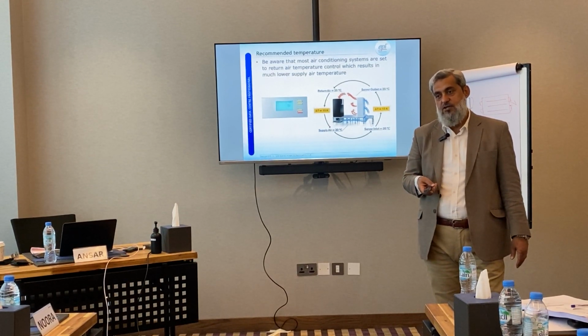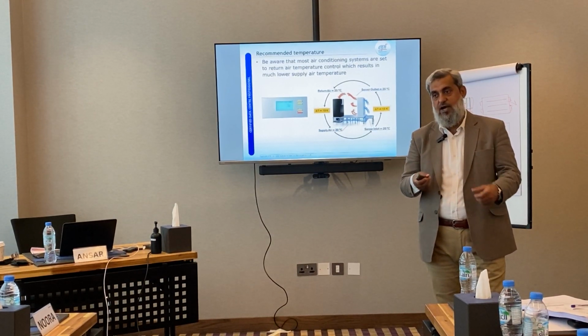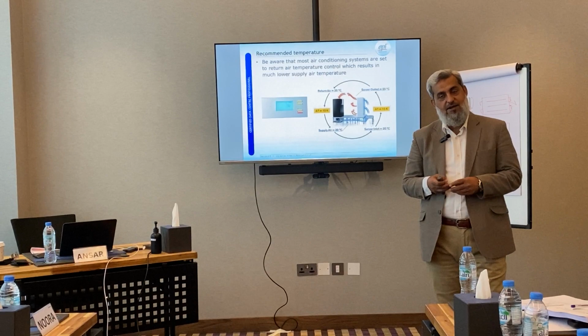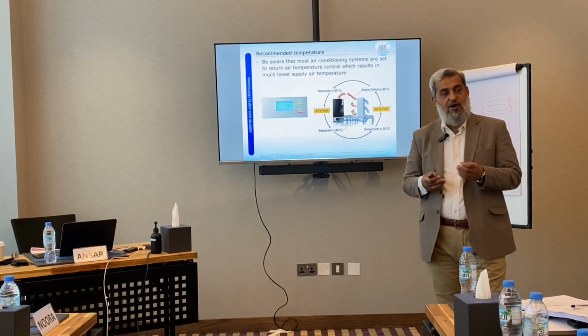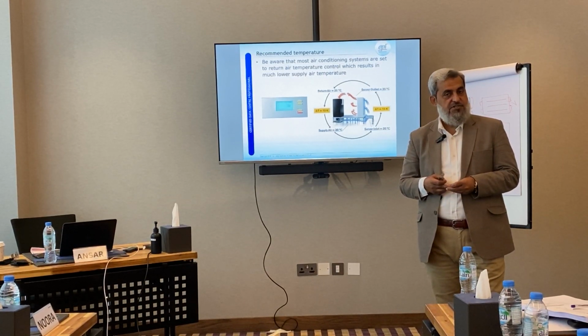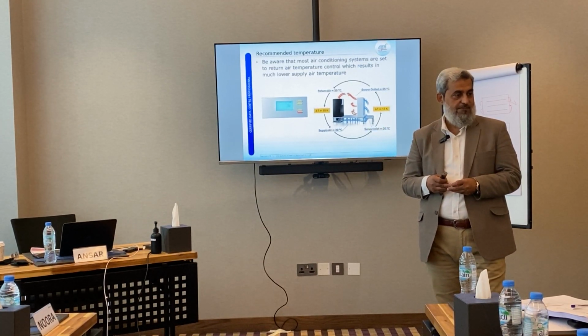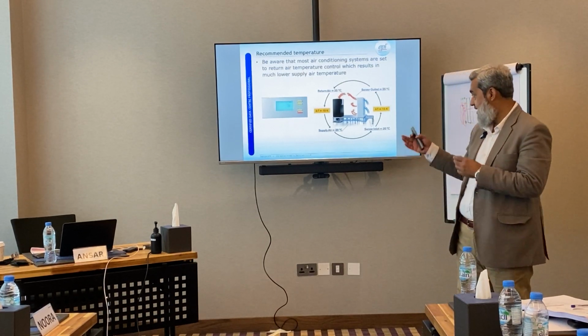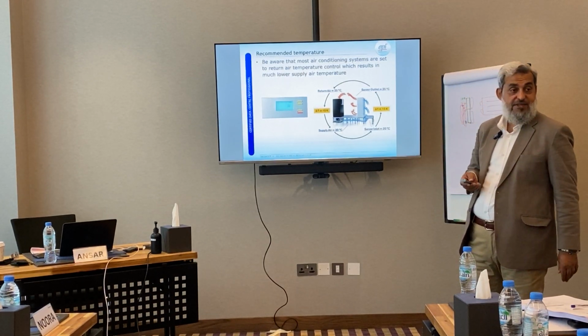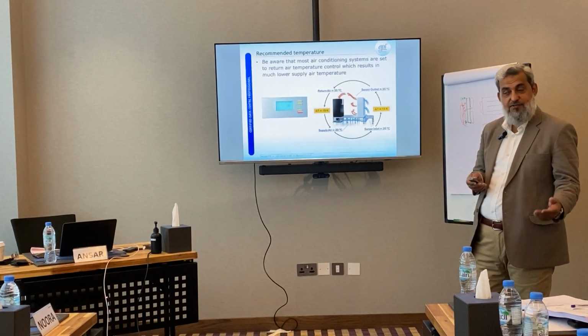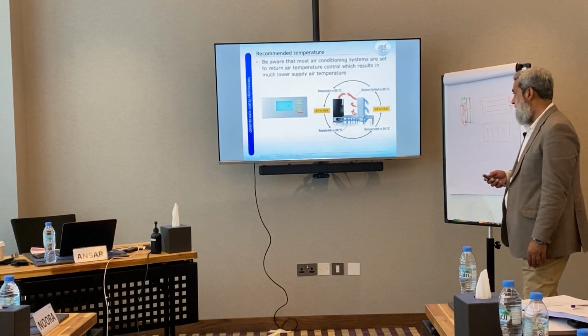Yeah, that's right. There are a lot of systems these days, the chiller systems come with a hybrid option. So even if out of 365 days, say 50 days or 100 days, you get a temperature which is below the threshold, you can take free cooling advantage.